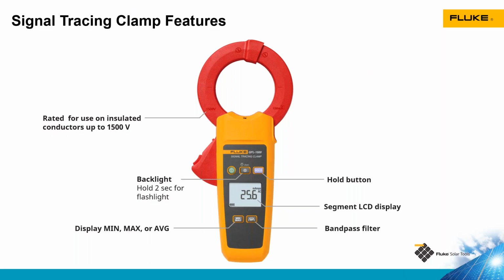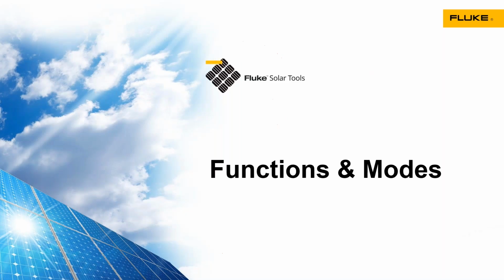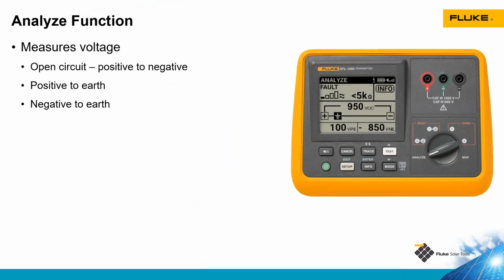Okay, moving along. Let's look at the functions of the tool and the different modes that we have as well. The analyze function is the first step in the ground fault troubleshooting process. It is going to do some voltage measurements, open circuit voltage, so it will tell you what the voltage between positive and negative is. And then it's going to measure positive to earth or ground and negative to earth or ground. And that's going to tell us if there is a fault present.